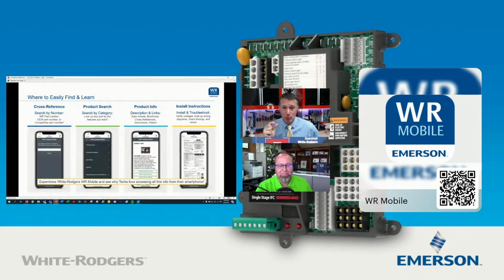If you want to teach flame rectification, utilize this style of board where we can see it. I love to teach it with a meter, but if we want to show it in quick reality, now's a good chance to have your meter to show how to read microamps on the board. Have a couple different flame rods handy, one really nasty corroded one and one nice and clean, and show the difference in current flowing through a dirty burner, a dirty flame rod, a poor connection, a bad crimp, a melted wire, and show how quick changes can affect that microamp reading and how it drops out when it gets low.